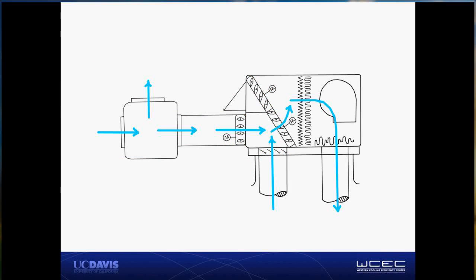This kind of gives you just an airflow schematic of how the system would be operating when you need some DX cooling. The VFD ramps up on the supply blower for the rooftop unit, draws some return air from the space. The fan and indirect evaporative system is operating, which is providing some air into the return plenum there. The pressure in the return plenum is negative, so that you'll draw air from the space into the rooftop unit.